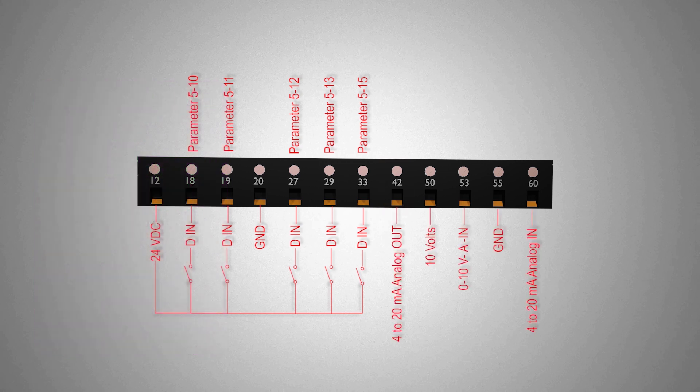Terminal 42 is here to generate an analog output which will be 4 to 20 milliamps signal. This signal can be programmed to show output voltage, current, frequency or the RPM of the motor.